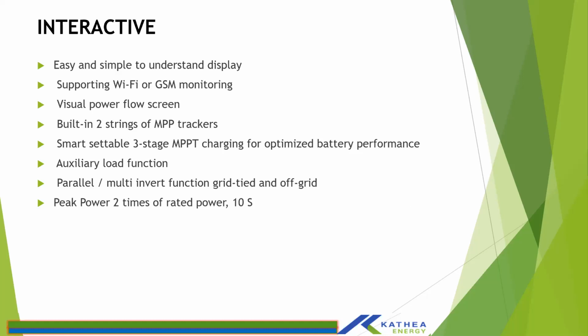And then the 8 kilowatt inverter comes with a 125 to 450 VOC and a 22 amp current rating. So if your PV array is quite big and the string length will be more than 450 volts, then you can connect 2 panels in parallel in a string. However, this means you would need a 2-to-1 combiner box before wiring to the inverter.